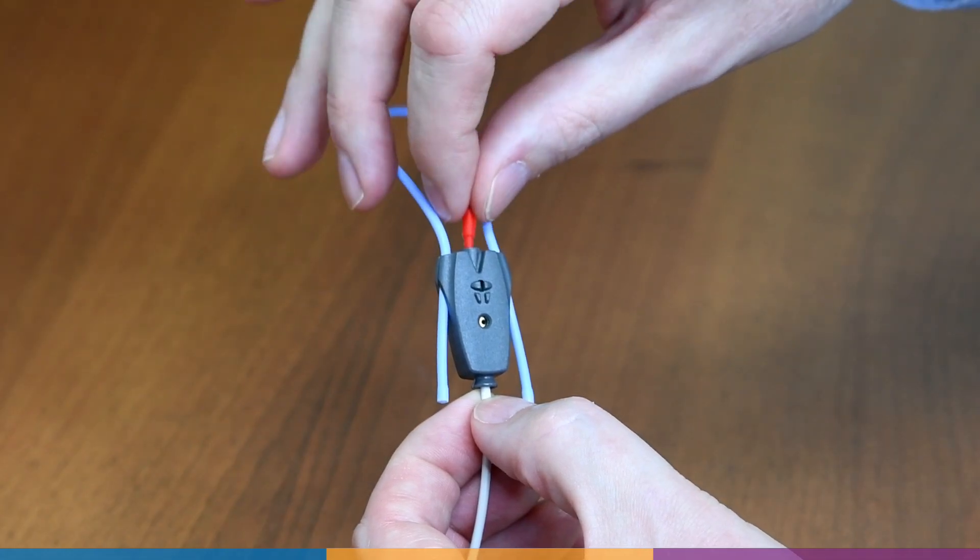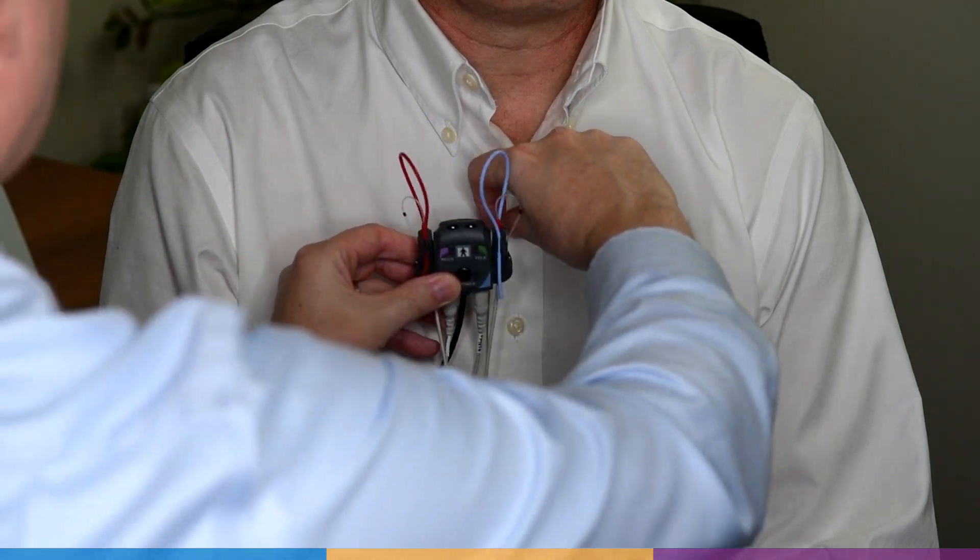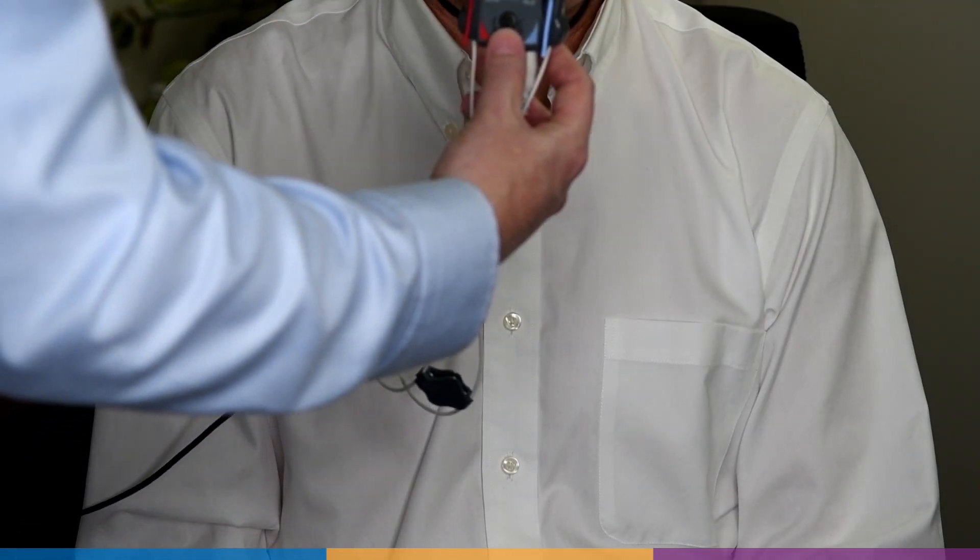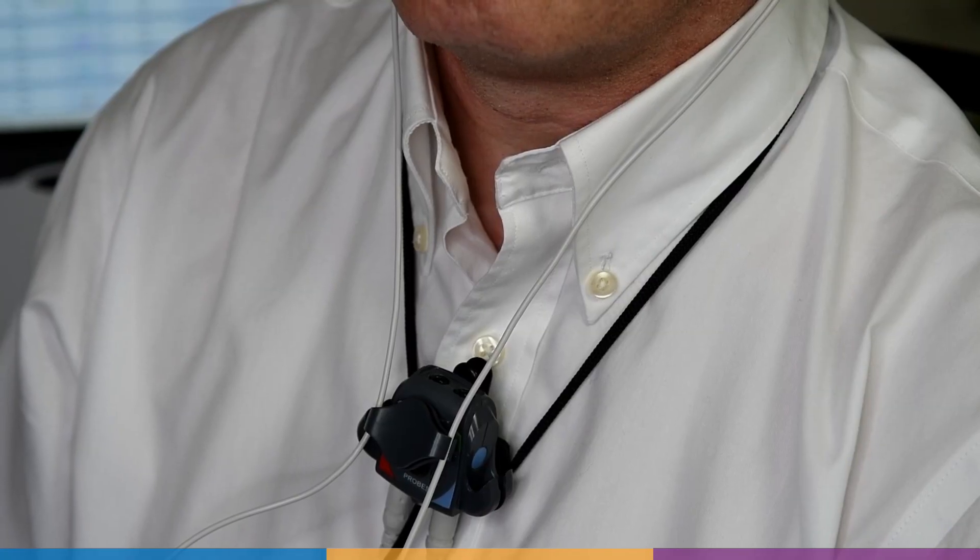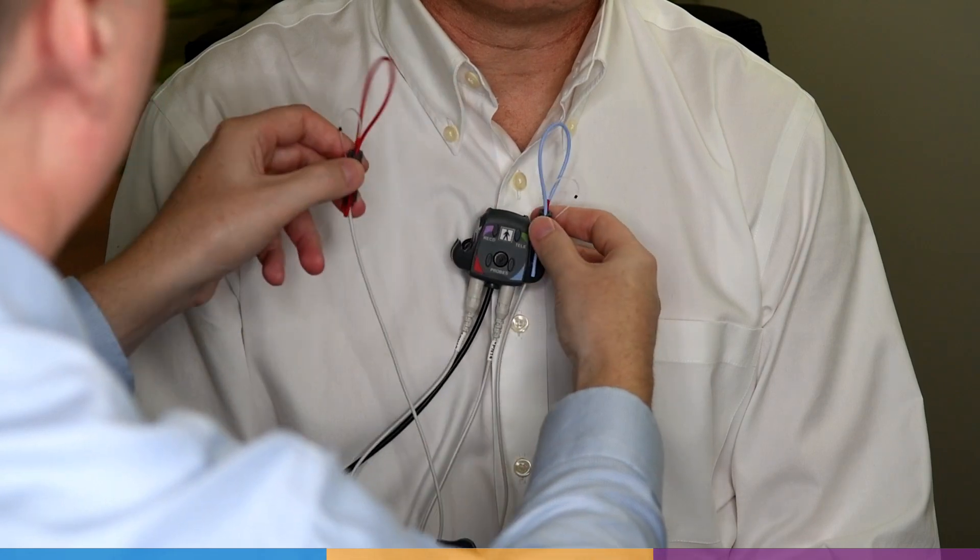Attach the probe tube to the probe module. For Verifit2, clip the probe dock to the client's clothing near the middle or to one side. If it's more convenient, it can be alternatively clipped to a lanyard or the chair back.